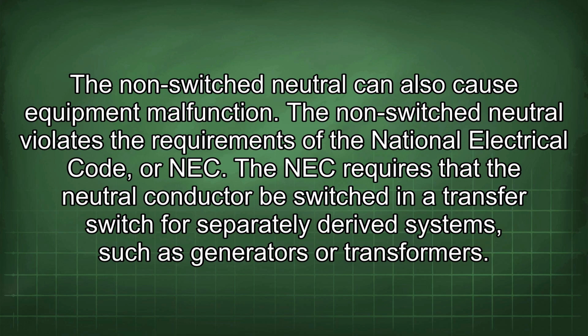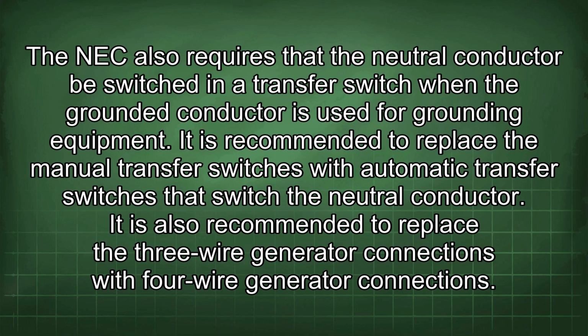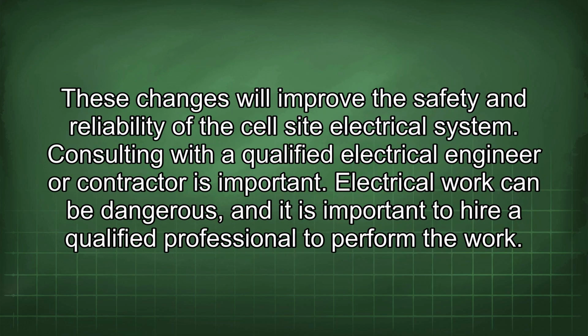The NEC requires that the neutral conductor be switched in a transfer switch for separately derived systems such as generators or transformers. The NEC also requires that the neutral conductor be switched in a transfer switch when the grounded conductor is used for grounding equipment. It is recommended to replace the manual transfer switches with automatic transfer switches that switch the neutral conductor. It is also recommended to replace the 3-wire generator connections with 4-wire generator connections. These changes will improve the safety and reliability of the cell site electrical system.